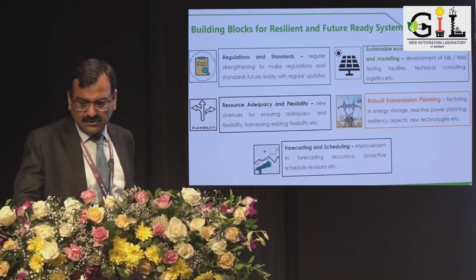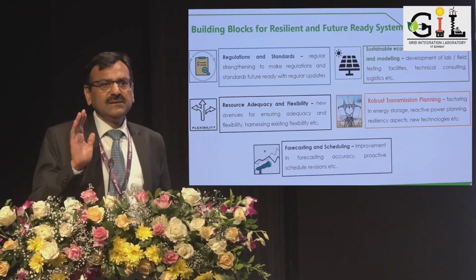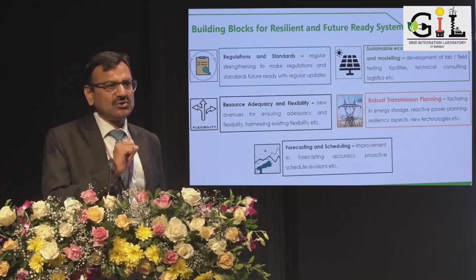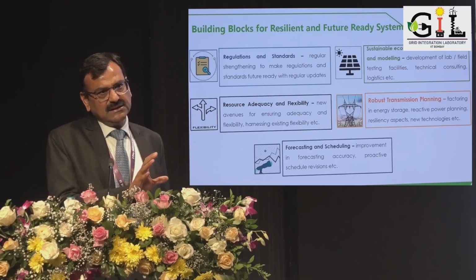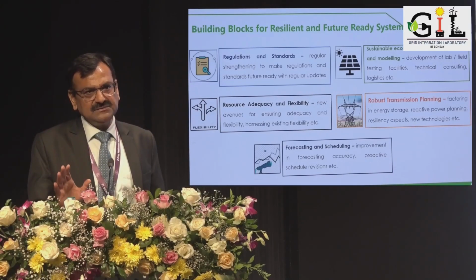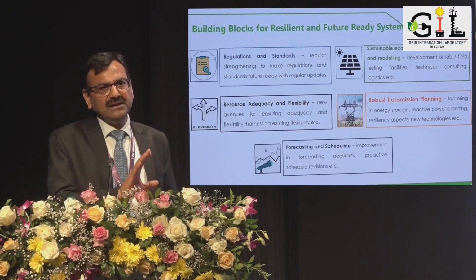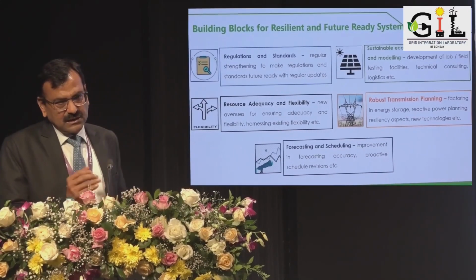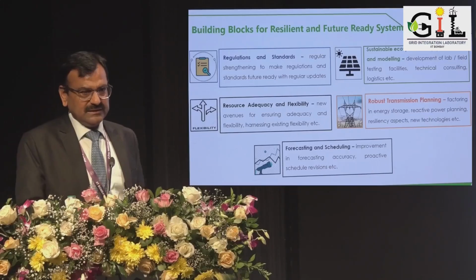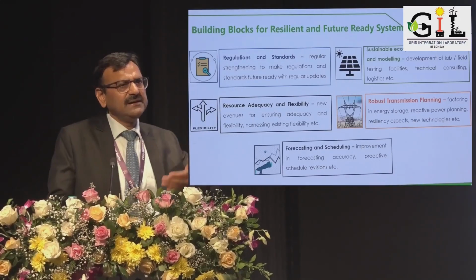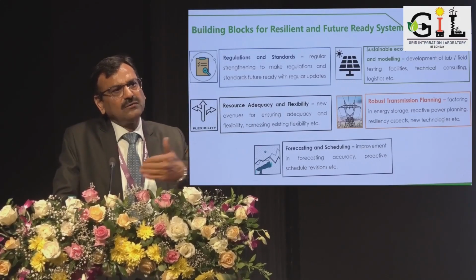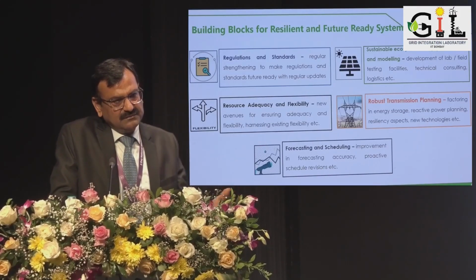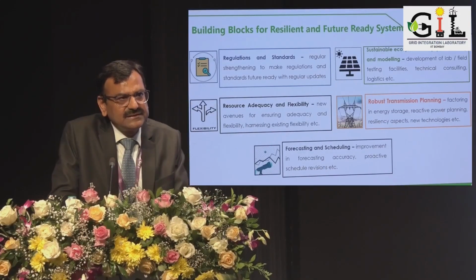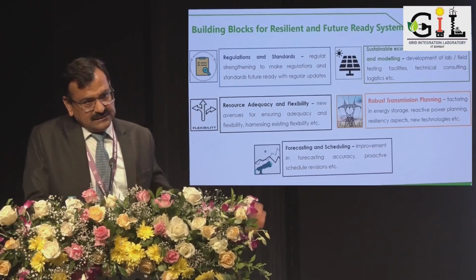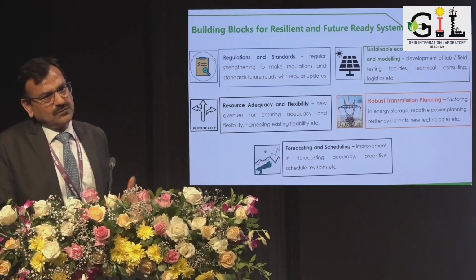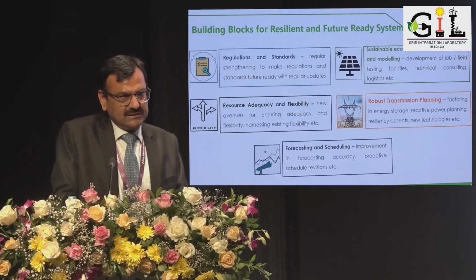Another area is the LVRT and HVRT response time. Though these regulations say that units need to ride through faults, the question is how much time they need to support - if any fault occurs, our machines need to give a lot of support to the system so that once the fault clears, voltage ramps up fast. But this voltage support from renewables has been a cause of concern.